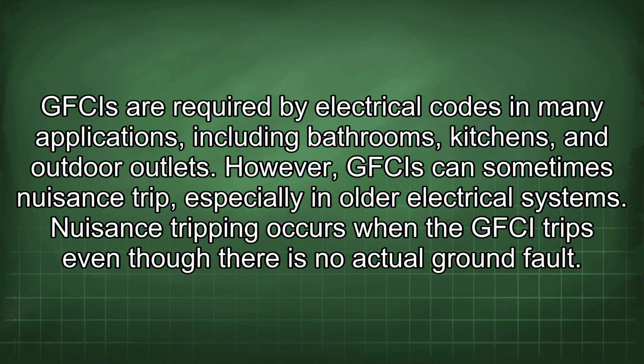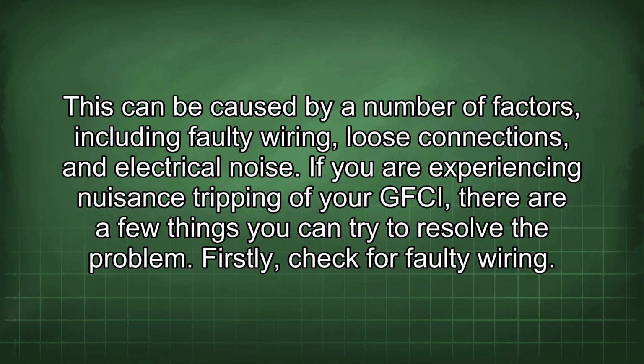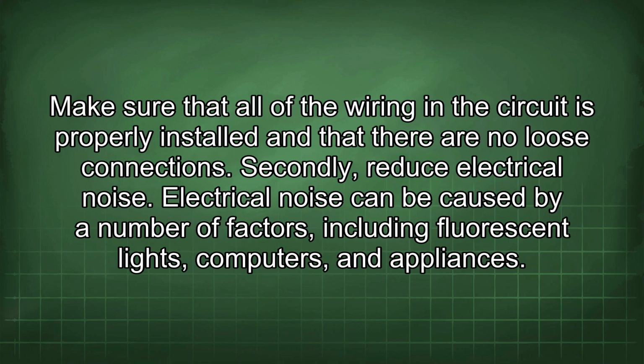However, GFCIs can sometimes nuisance trip, especially in older electrical systems. Nuisance tripping occurs when the GFCI trips even though there is no actual ground fault. This can be caused by a number of factors, including faulty wiring, loose connections, and electrical noise. If you're experiencing nuisance tripping of your GFCI, there are a few things you can try to resolve the problem. Firstly, check for faulty wiring. Make sure that all of the wiring in the circuit is properly installed and that there are no loose connections.